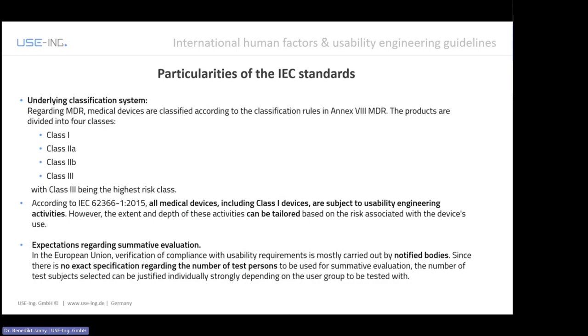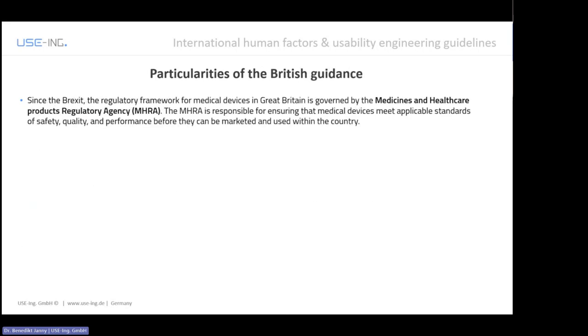Okay, so this was the first deep dive of the IEC standard. Let's come to the second one. As mentioned before, since Brexit, the regulatory framework for medical devices in Great Britain is governed by the Medicines and Healthcare Products Regulatory Agency, the MHRA. The MHRA released a guidance titled Guidance on Applying Human Factors and Usability Engineering to Medical Devices, including drug devices, combination products in Great Britain.